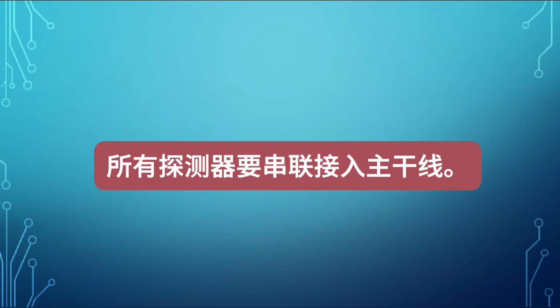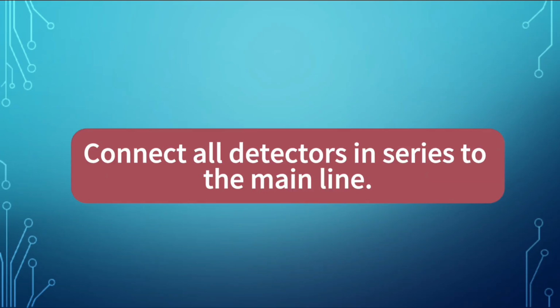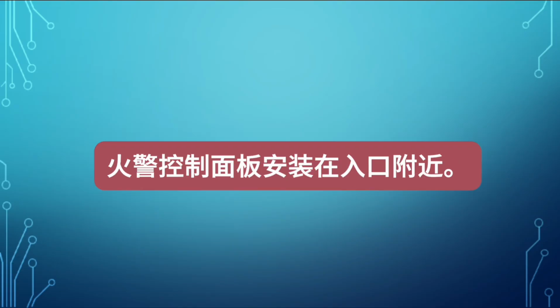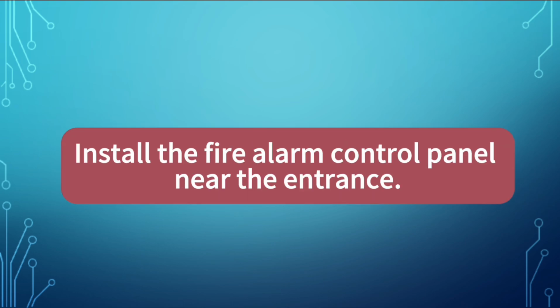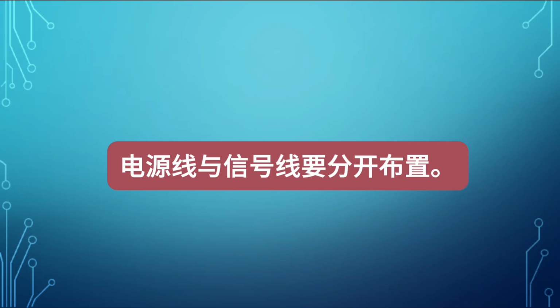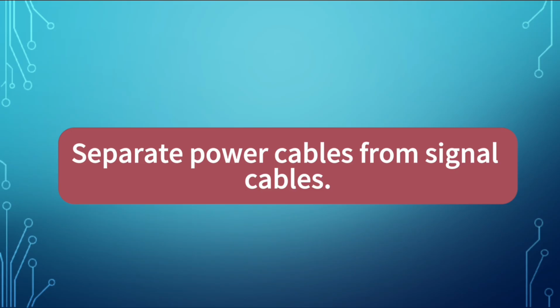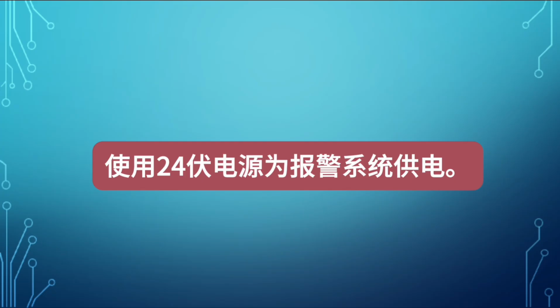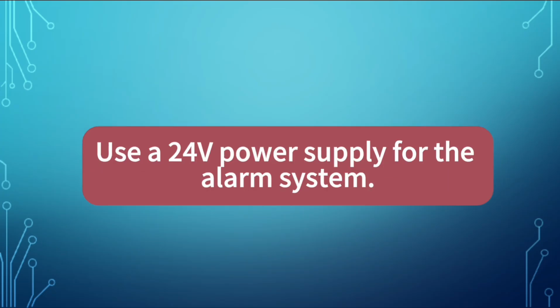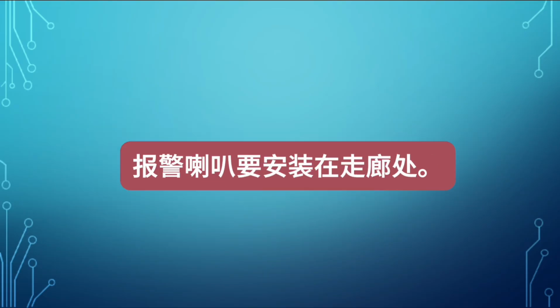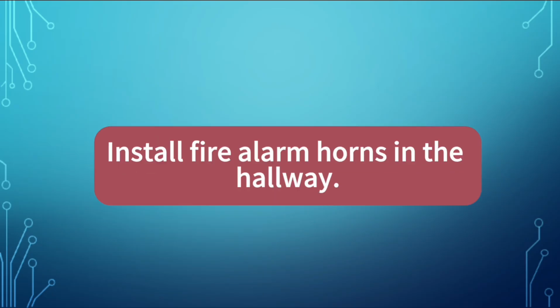Connect all detectors in series to the main line. Install the fire alarm control panel near the entrance. Separate power cables from signal cables. Use a 24-volt power supply for the alarm system. Install fire alarm horns in the hallway.